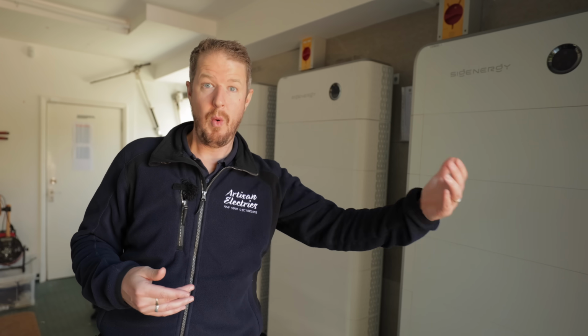It can be up to 100 kilowatt on 3-phase. Single phase is usually a lot less. So within that restriction, we might need to lower the size of the inverters to meet their requirements while still enabling us to charge the batteries within that cheap energy window. So as you can see, there's quite a lot to factor in, but if you get a good installer who knows what they're doing, then they can design the system to meet your needs, but also the requirements of the DNO.